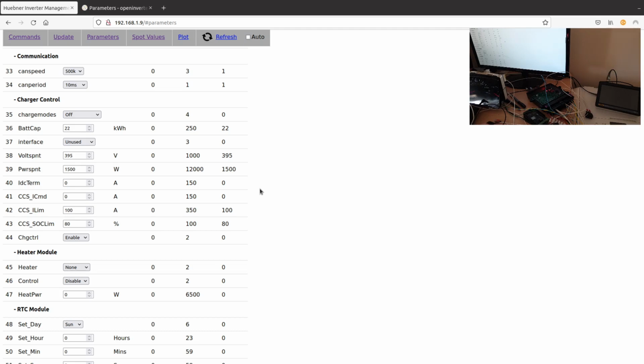Charger control is where we can set up things for our battery charging. Charge modes: we have off, HV on - just a manual way of requesting the VCU to initiate an HV startup - external CAN, which allows us to command the charger via CAN and receive from the charger via CAN, and external digital, which allows us to do the same but with a 12 volt signal, such as HV request that we saw earlier. The volt ampere option will hopefully be implemented soon for controlling a Chevy Volt Opel Ampera charger directly. Battery capacity is where we put our battery capacity in kilowatt hours, used basically for calculating SOC.